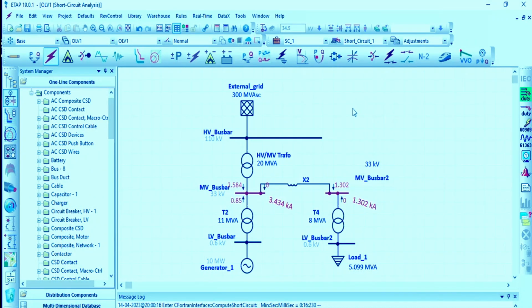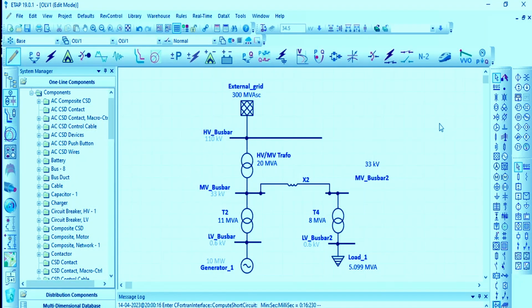So we are doing a nice analysis. So maybe when we have a project, or maybe when you have a study to do, you say that okay, we have learned in the course that to reduce the short circuit power, we need, for example, one or two or three, let's say, methods, and those methods are just increasing the resistance or the impedance, and this can be made by increasing cable length, by adding current limiters, reactors, and splitting the network.